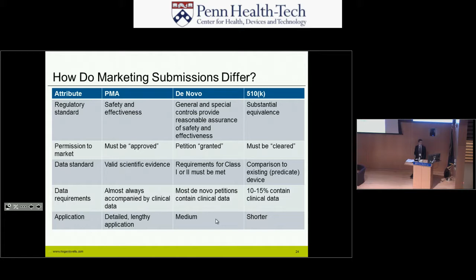Just for a little bit of background, confidentiality. For your pending PMA, it's confidential. What's going to go up online afterwards is a summary of safety and effectiveness. Similarly, with the de novo, the pending de novo is confidential, but you'll get an approval letter and you'll have a publicly disclosed decision summary, which is basically going to outline a lot of details about your device. 510K also confidential while pending, and what goes up is a 510K summary, which if you've ever looked at them from what they were 10 years ago to what they are now. 10 years ago, you hardly could tell what the device was when you read one of these because it was maybe 1 page long. Now they're requiring a lot more information. They're about 5 to 6 pages and go into significant detail about what type of testing was used.